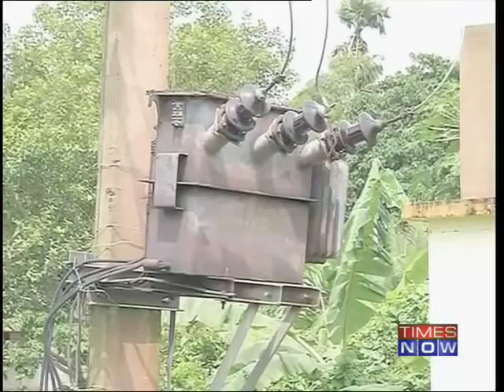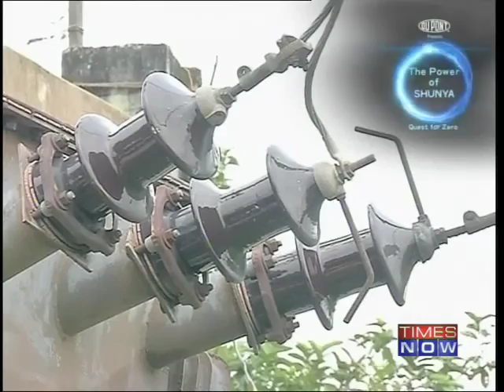These days, dry type transformers, specifically Nomex paper made transformers, are helpful. Firstly, because there is no oil in them, transformer failure can be reduced substantially, rather eliminated with no use of oil. Because of its property of withstanding high temperatures, and because of fire resistance, the paper prevents fire and withstands high temperatures while maintaining its dielectric strength.